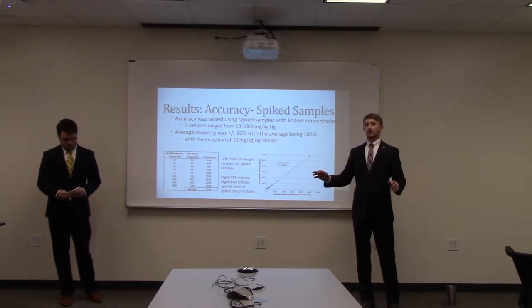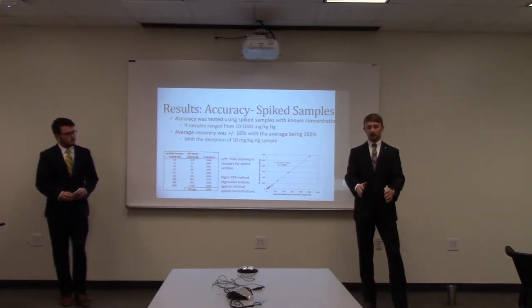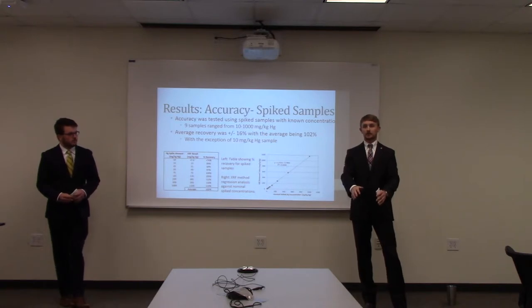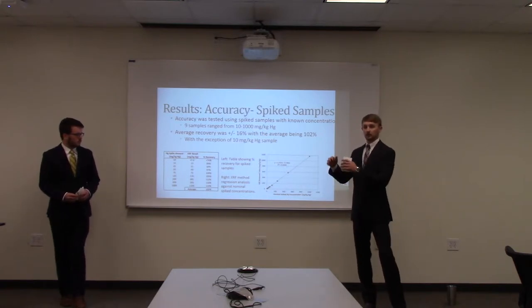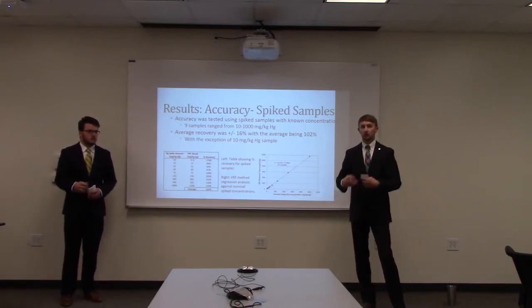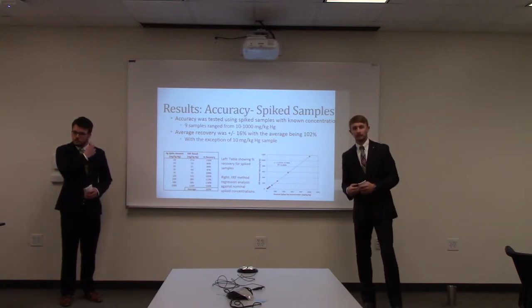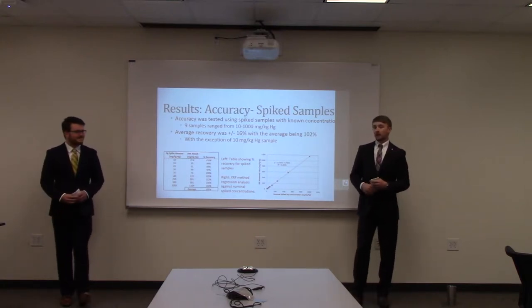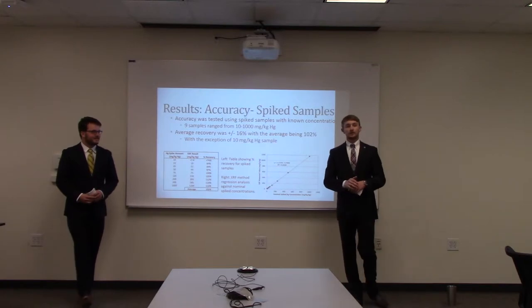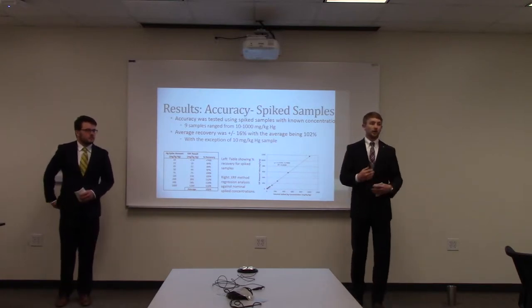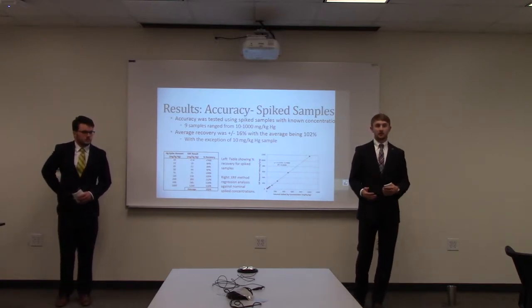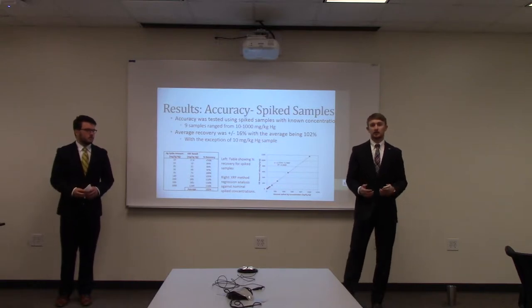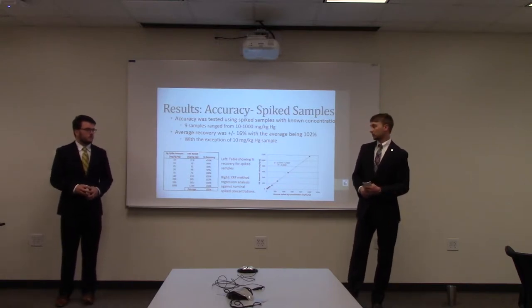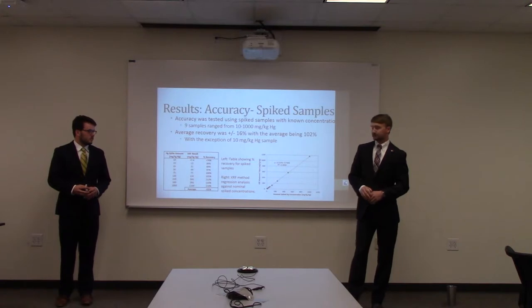So 100% recovery would mean that we know there's 10 milligrams per kilogram of mercury in this soil sample, and we were able to detect 10 milligrams. So it's 100% of that was able to be recovered by our device. And we found that our average recovery was 102%. So we were able to recover 100% of the mercury that we thought should be there, and we were only off by 2%, overshooting it just a little bit.